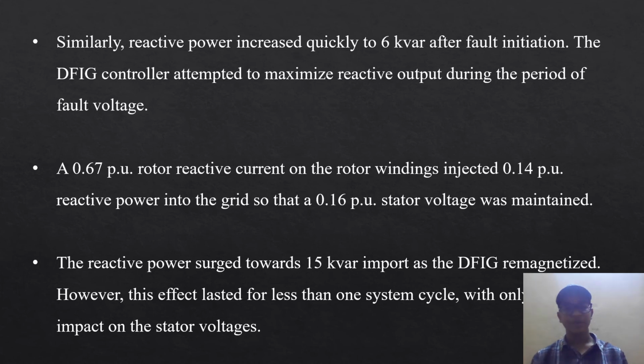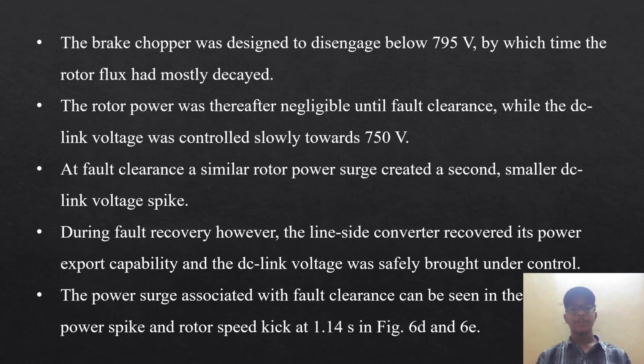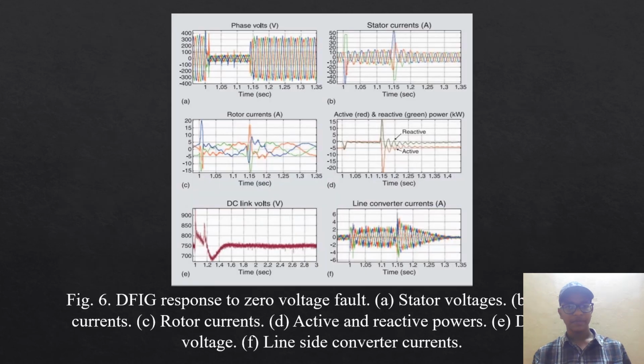A 0.67 pu rotor reactive current on the rotor windings injected 0.14 pu reactive power into the grid. A 0.16 pu stator voltage was maintained. The brake chopper was designed to disengage below 795 volts, by which time the rotor flux has mostly decayed. At fault clearance, the rotor power surge created a second, smaller DC link voltage spike. Here is a figure showing the DFIG response to the zero voltage fault.